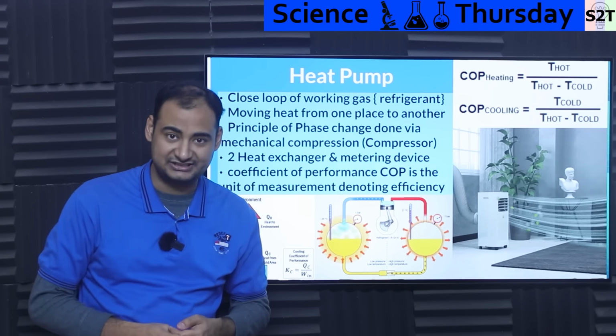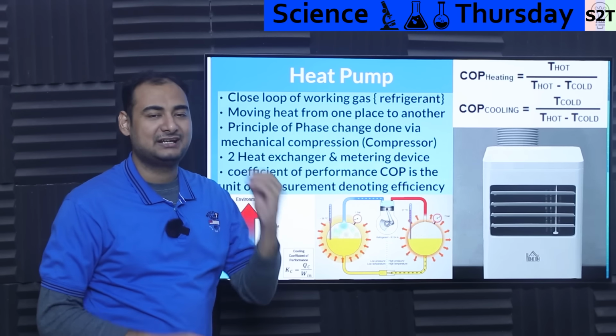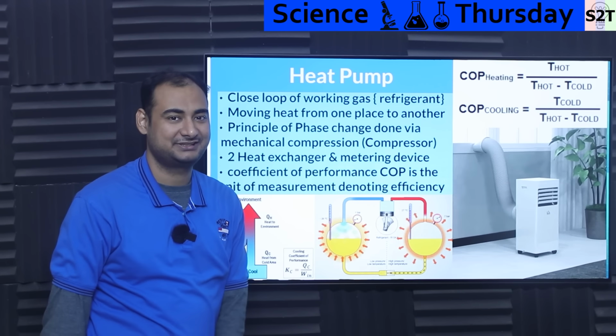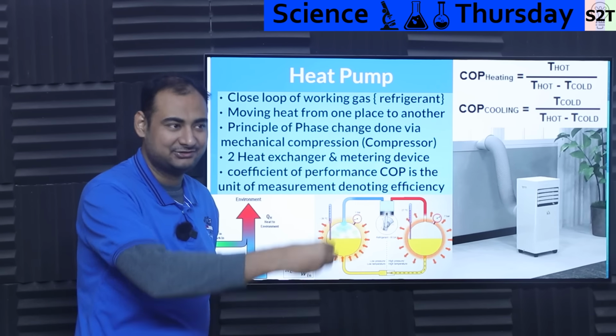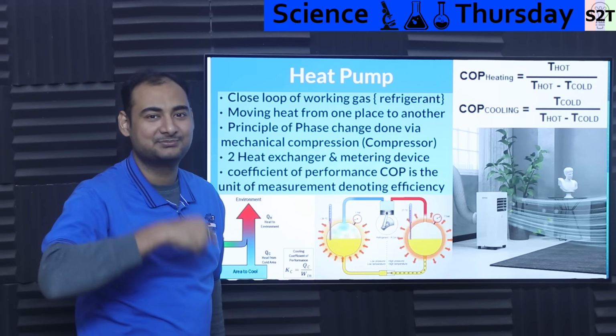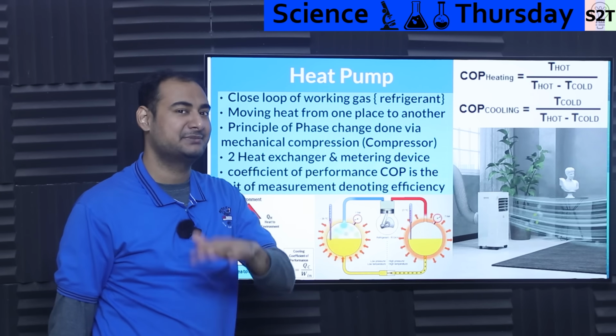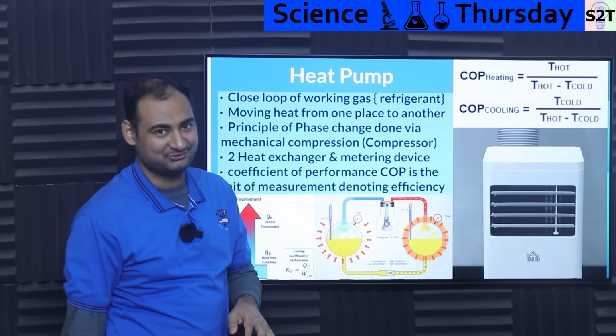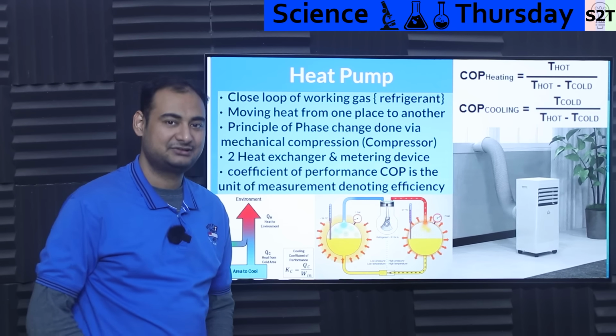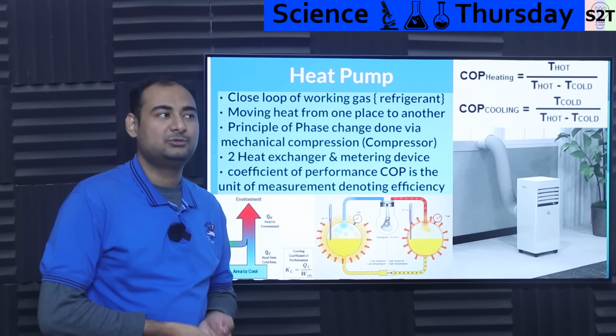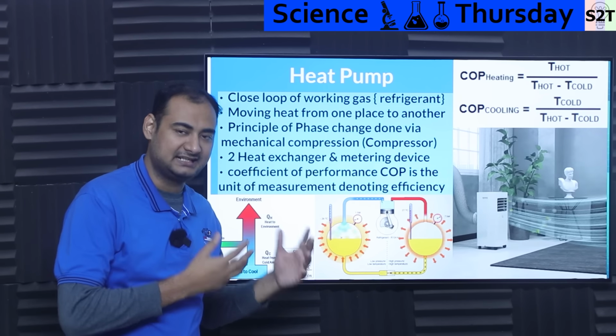If you have 5 COP, it is so much that you cannot consume the fuel and get more energy out of it. It would be better to use that fuel, generate electricity, run a heat pump, and you still would be efficient. But again, that generally happens above 4. It does not happen below 4. 2, yeah, it's not that effective. 2 is just effective as in, yeah, it would be better to consume less electricity.